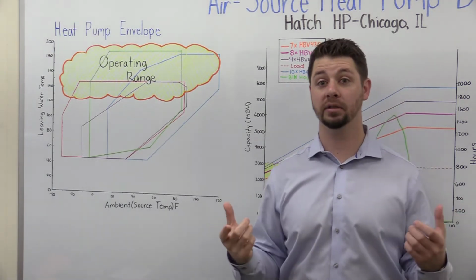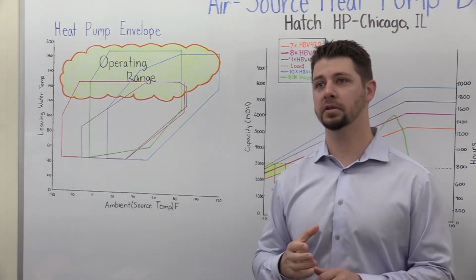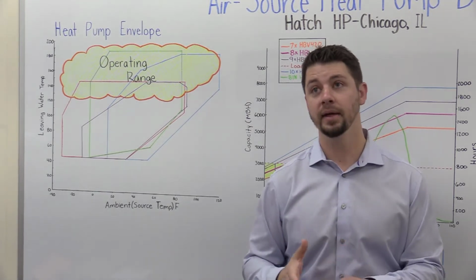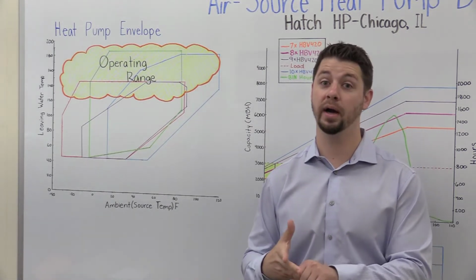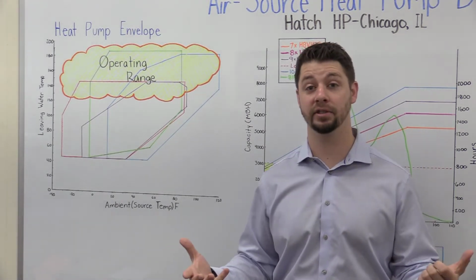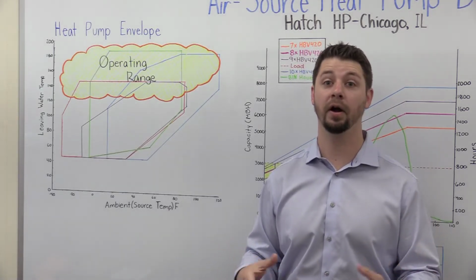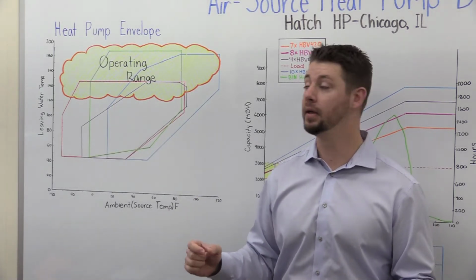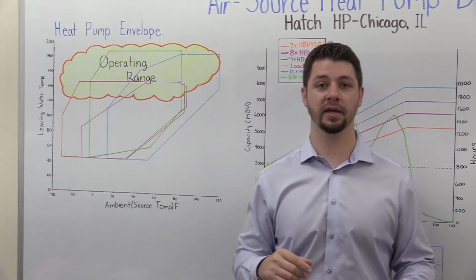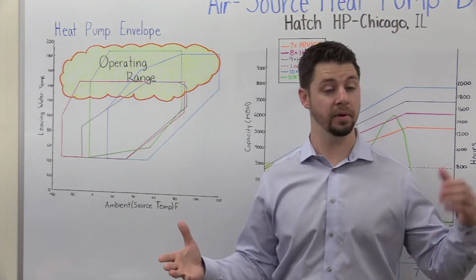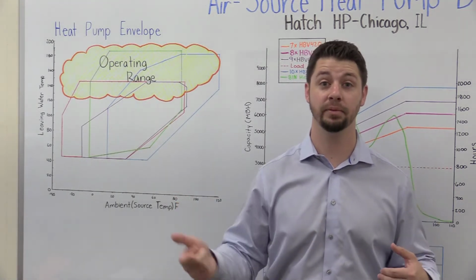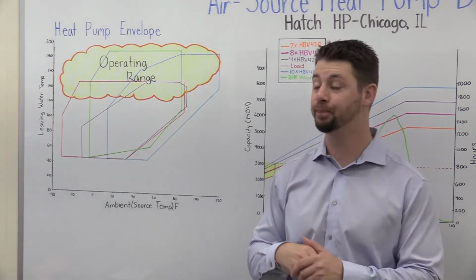What I want to stress to you is to understand your low-end demand and your high-end demand required of your compressors, and have a conversation with your equipment vendor about where you're operating, because this is critical to understanding not only peak demand, but also part load demand of when you need to be capable of producing hot water.